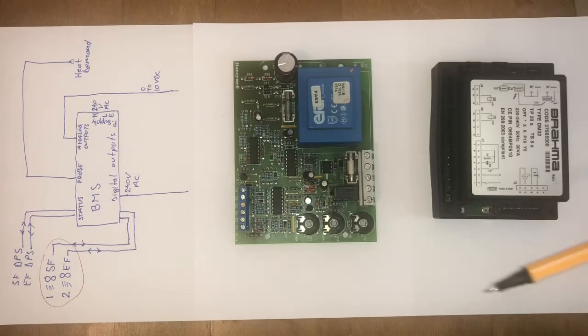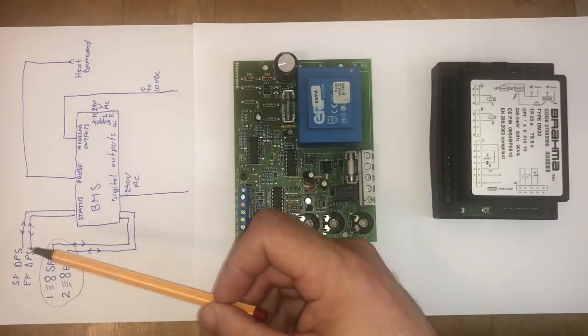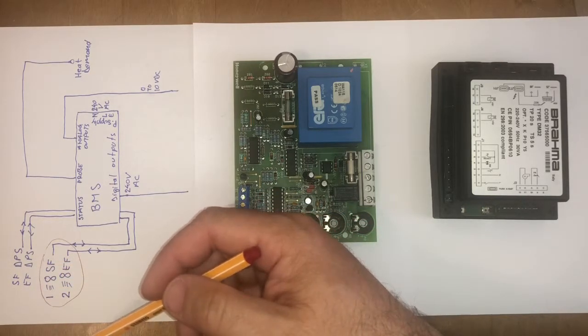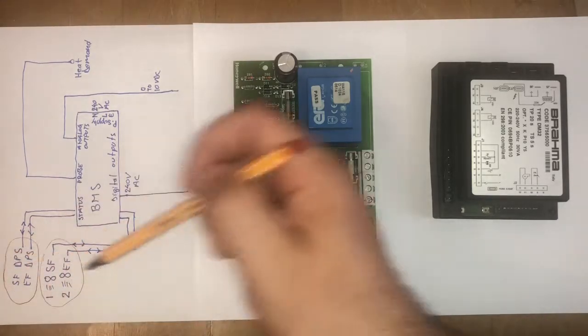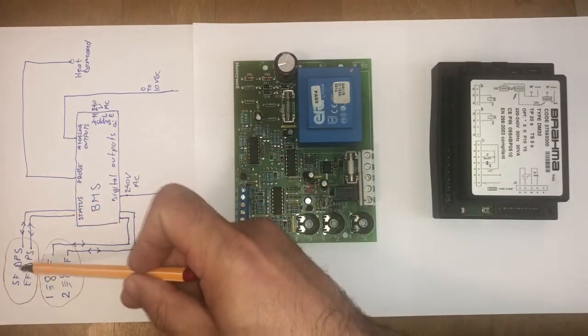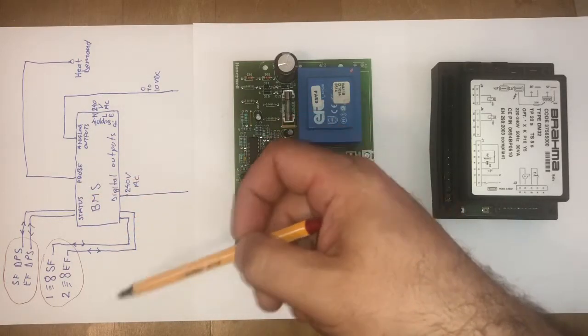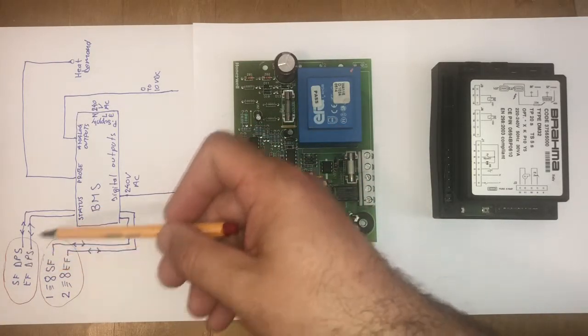They need air, otherwise they will overheat, and then the high limit will disconnect the burner and the flame will go off anyway. But that's not an appropriate way to do it. So first you have to start the supply and the extractor fan. If the supply and the extractor fan have the appropriate condition as per the differential pressure switch setting, then the differential pressure switch will send a signal back to the building management control, telling it that okay, the fan runs, we know it runs because we have the right pressure. So as a DPS, we close the circuit, we send you the signal back, you can go further.